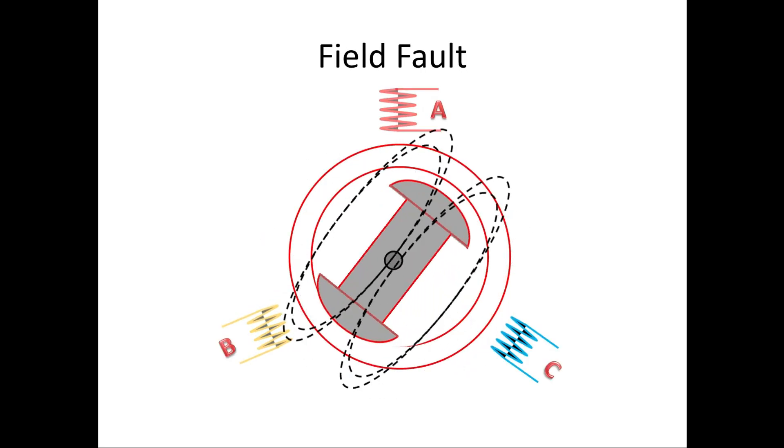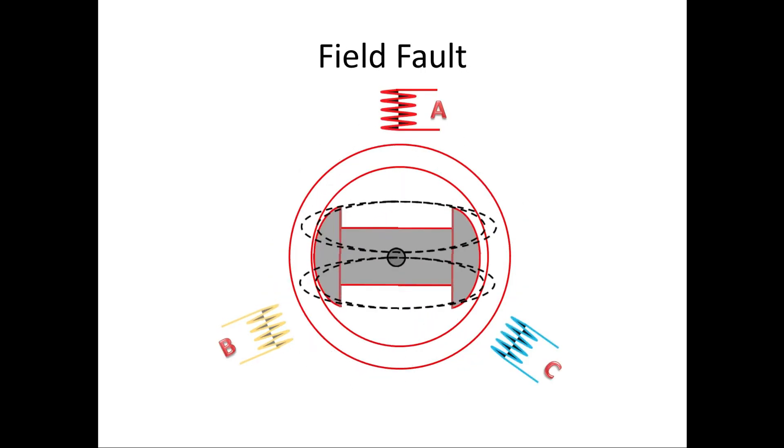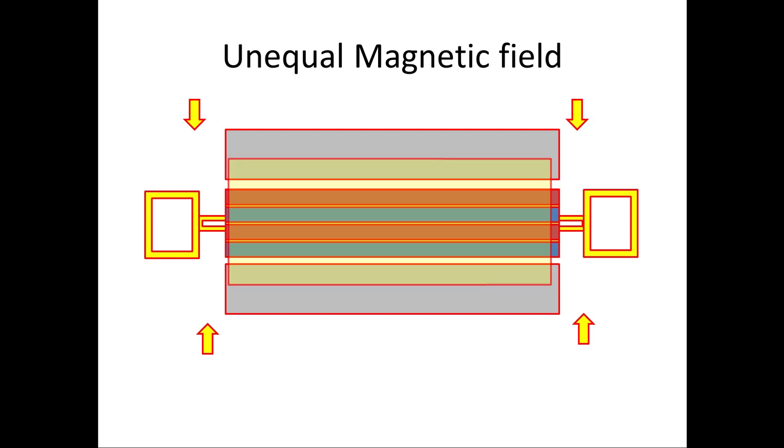For Rotor we have many protections. We are going to see earth fault protection. When we see the effect of earth fault on the rotor, first it reduces the magnetic flux on rotor, which affects the output of Stator. Second it makes magnetic imbalance on rotor, which leads to vibration and bearing failure due to the force imbalance on rotor.